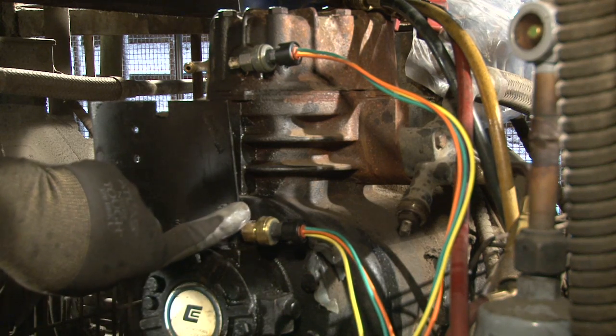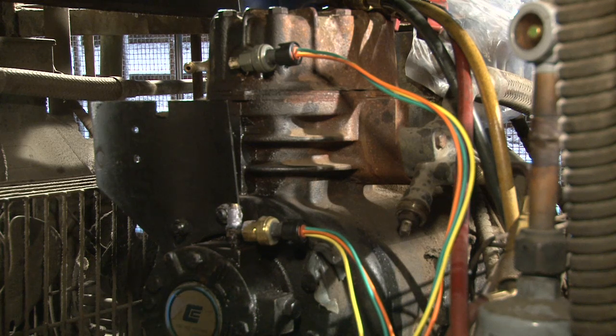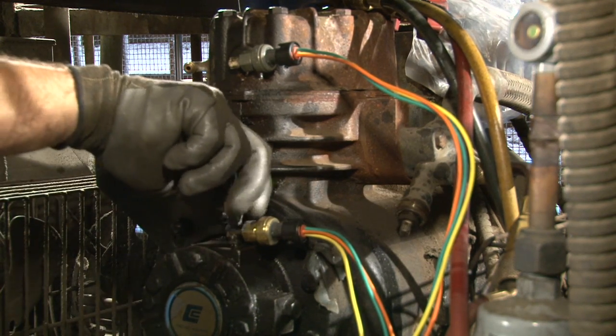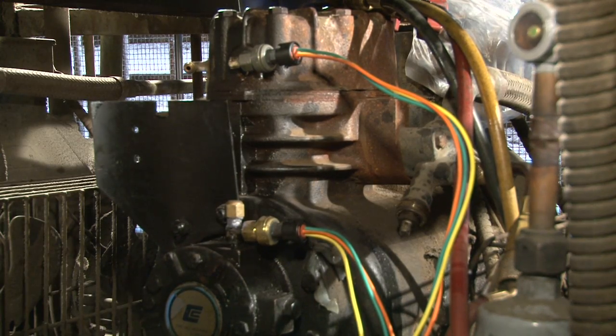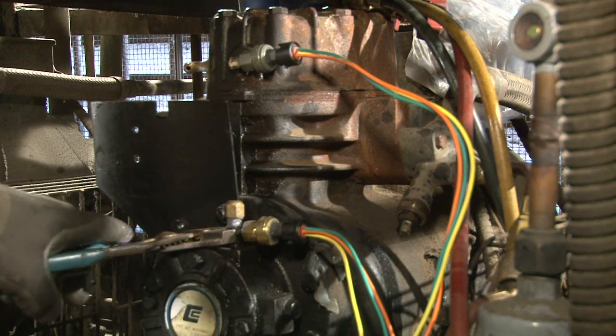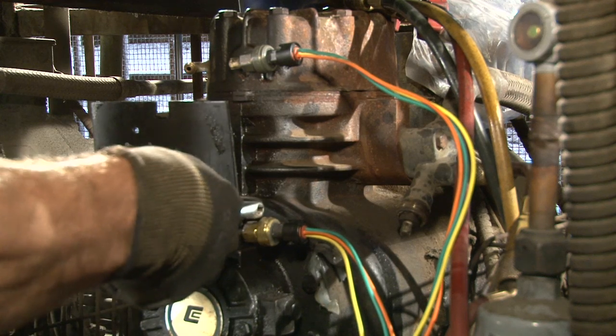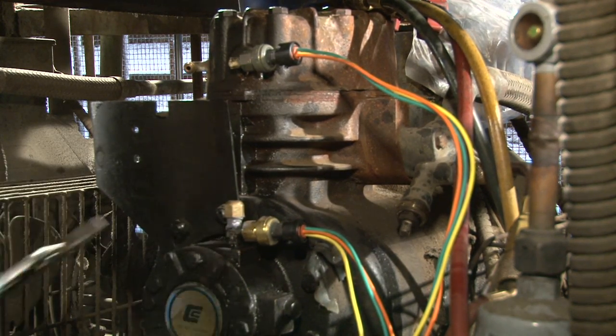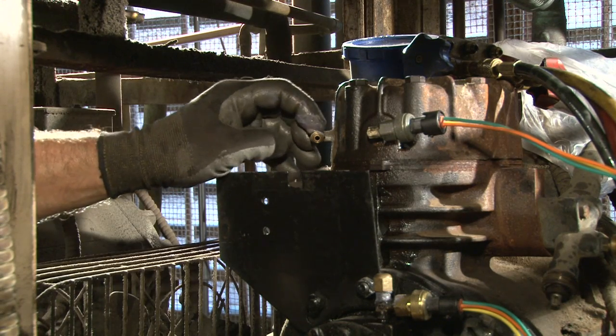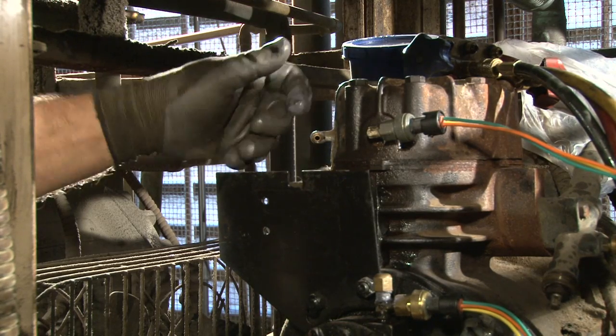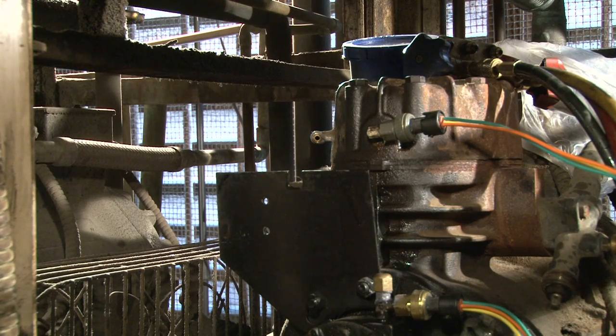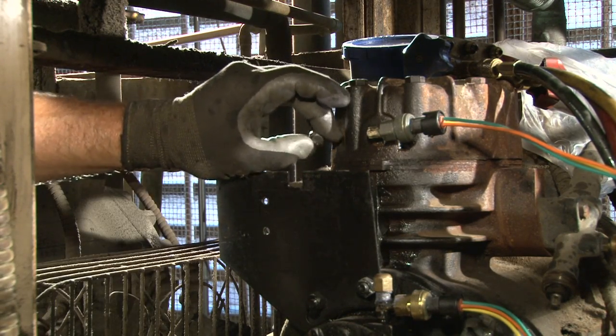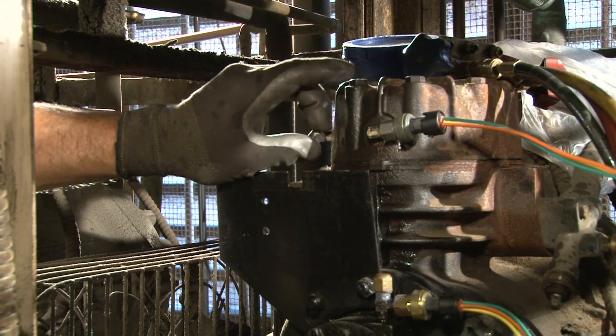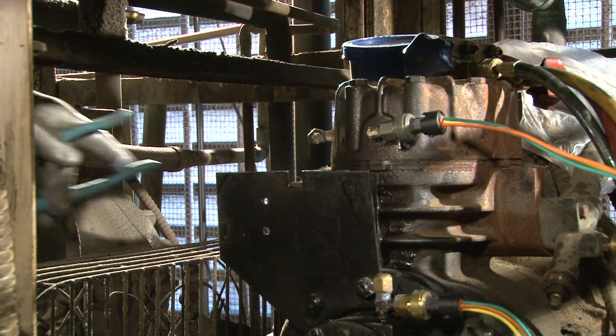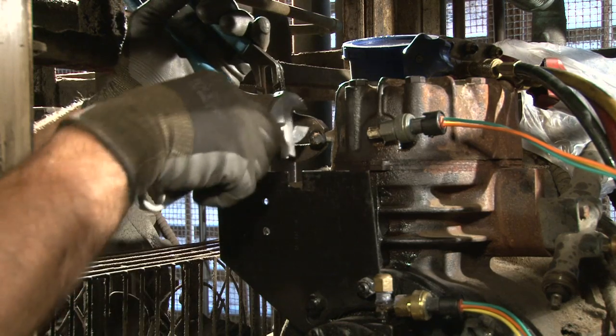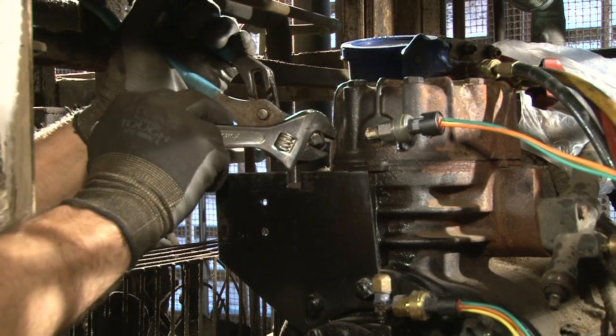Prior to having done that, in particular on the oil discharge second adapter fitting on the pump, the technician used a leak lock compound in order to ensure that there would be no leakage even after the flare cap is tightened down with the wrench. Here the technician is applying the compound onto the low pressure fitting on the compressor head. In this particular case, this is an extra fitting and will no longer be needed. So the technician is threading a blank threaded cap onto the fitting. Using the channel locks as a backup wrench, he uses a small adjustable wrench to tighten the cap securely.